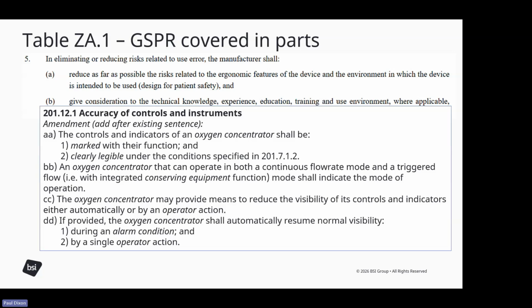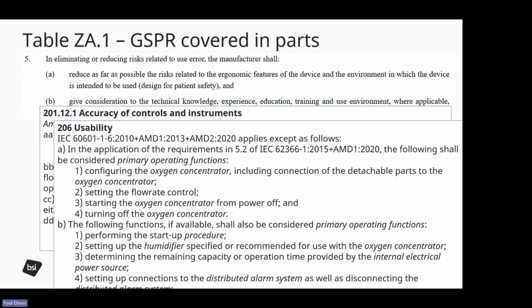We have an accuracy of controls and instruments clause that references both the clarity and legibility of the markings, which addresses to an extent 10.5a, and it has a number of sub-clauses that refer to the way in which it is operated. And we also have a usability clause, 206, which discusses primary operating functions. So, configuring the oxygen concentrator, setting flow rate.